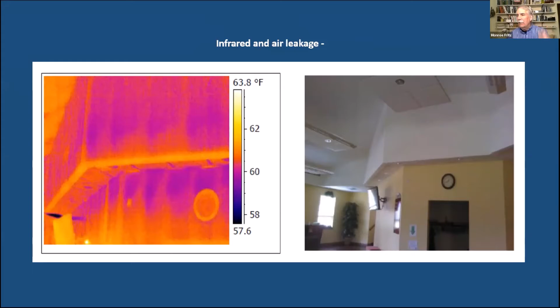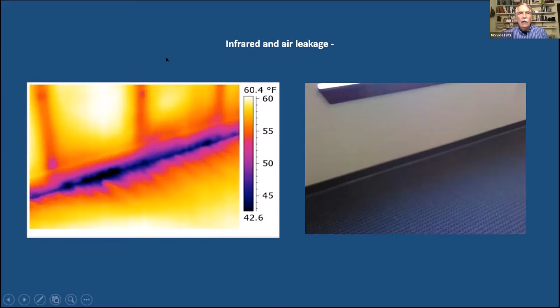Moving to this next example, a classic case: air barriers leak where big major air components come together, such as walls and floors. When you see blaze marks across this carpet, remember infrared does not see moving air. But when air moves in and infiltrates aggressively, it creates that blaze mark as it cools the top surface of the carpet, and the infrared sees the evidence of that invading, flowing air as it comes across into the room. This is an infrared picture of an air leak in a building.